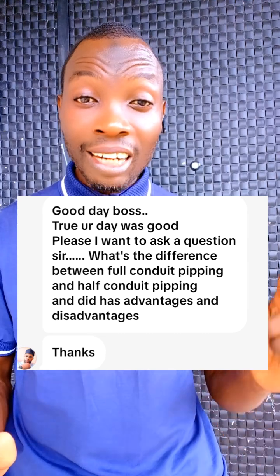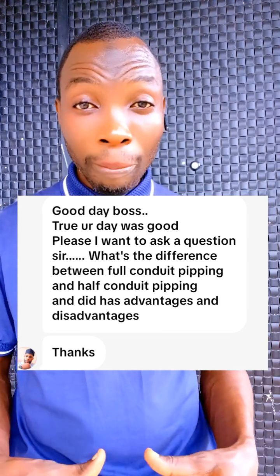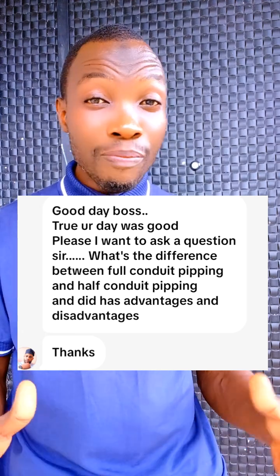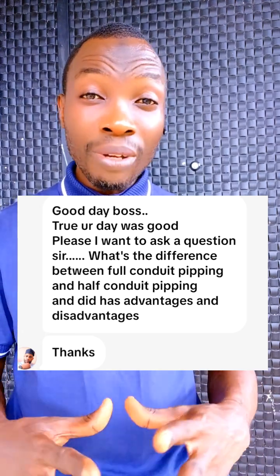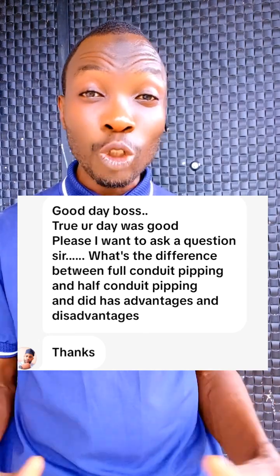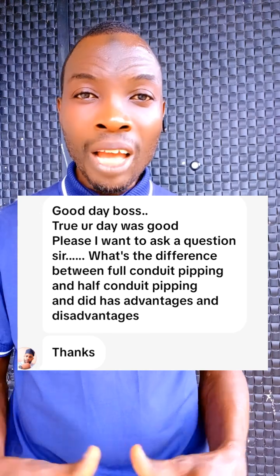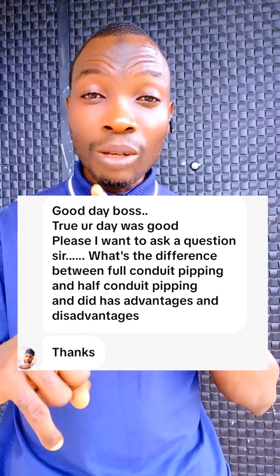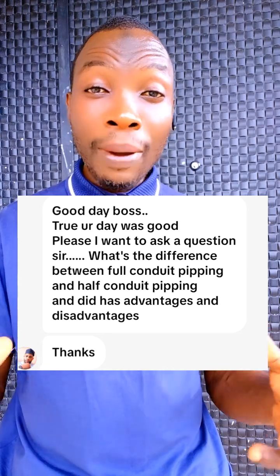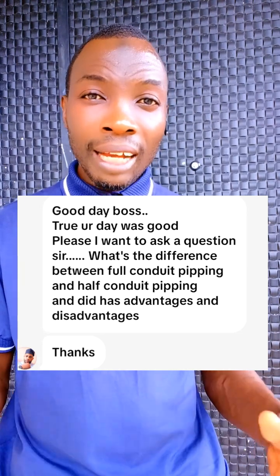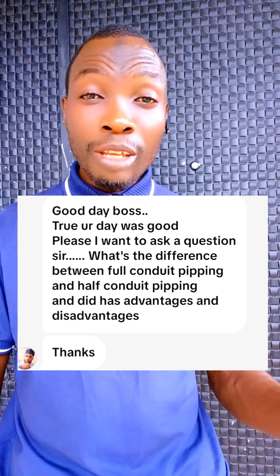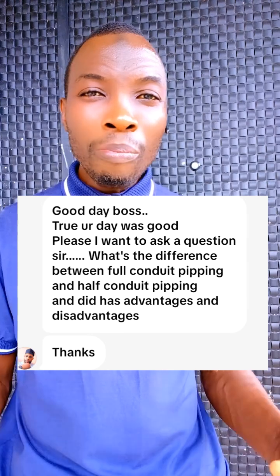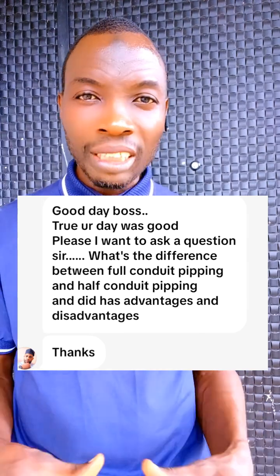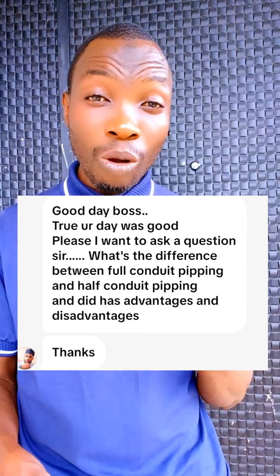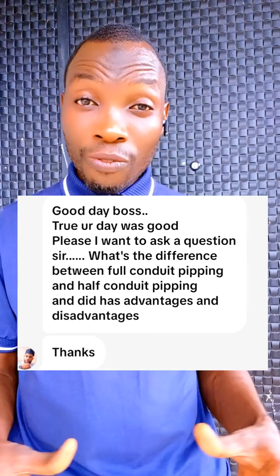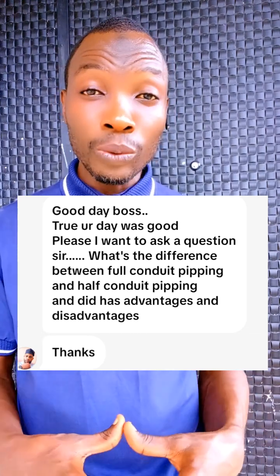Rodents, rats in that area, they are like human beings. If you see their sizes, they are big. They found their way into the roof and finished up all the insulation of the cables. As a result, conductors were lying over one another and thereby created a short circuit. That has been the reason why the breaker continued to trip. We met a lot of cables destroyed. It was since that time I concluded in my mind that full conduit is better than half conduit.